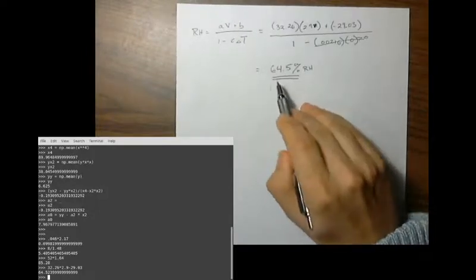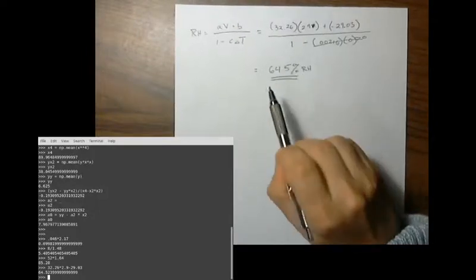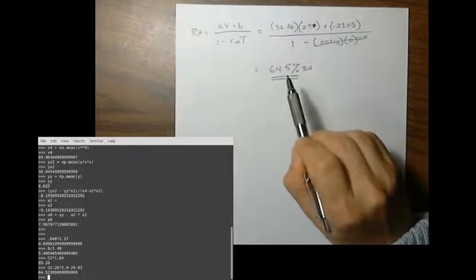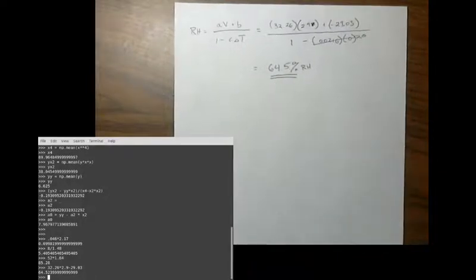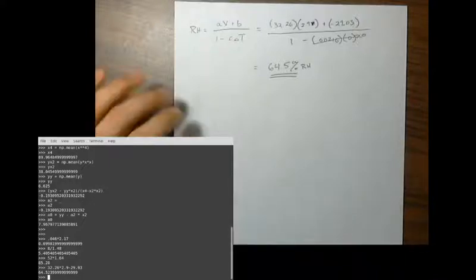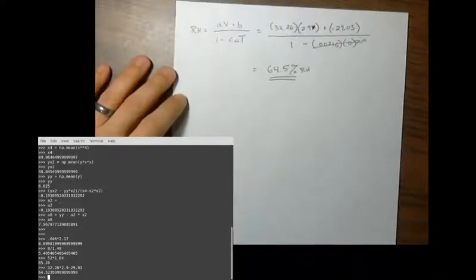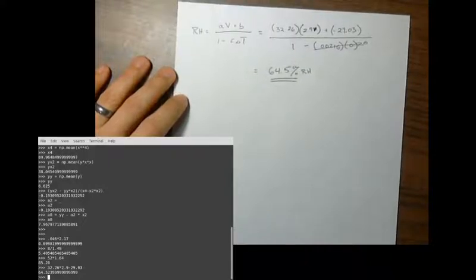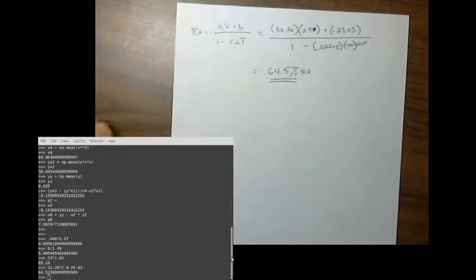But really the biggest problem for buildings is that at high humidity you run the risk of mold growth, as mold can survive in the building, and that's not good. So the reason you want to keep humidity under control is that you typically want to keep it between 40 and 60%, according to the guidelines I've read. Okay, so this is a little humid, but not unreasonable.